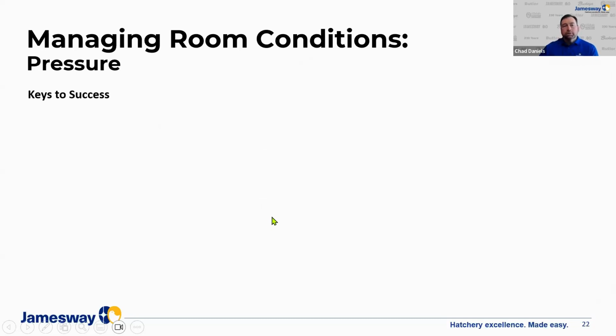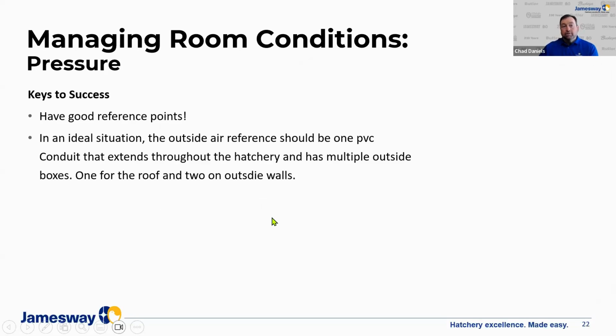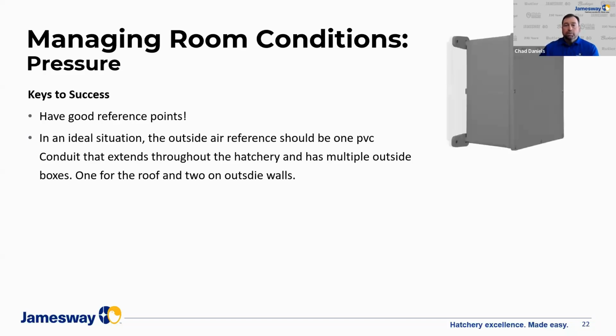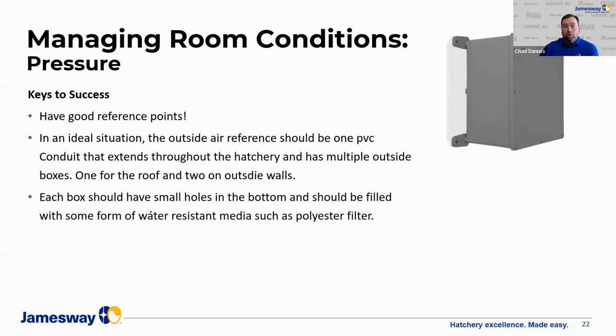So, keys to success when managing room conditions and pressure: have a good reference point. When we talk about reference points, an ideal situation is the outside air reference should be one reference conduit, or PVC conduit, that extends throughout the hatchery and has multiple outside boxes, preferably one for the roof and a couple on outside walls. Typically, that's just going to be a small plastic or PVC box, and you'll put small holes in the bottom of this box, and then you'll fill this box with some type of polyester media that does not absorb moisture. And the media just helps dampen some of the bounce that you'll see with wind gusts or wind blowing.